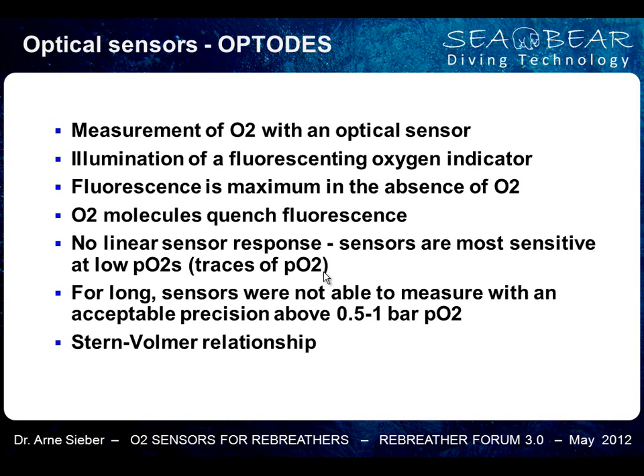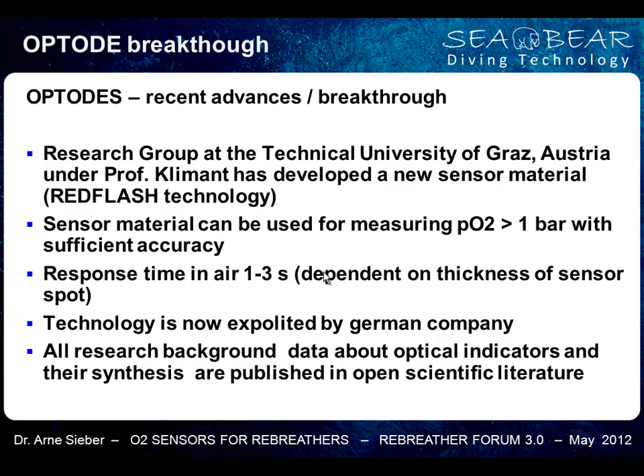Sensors like this have been available for a long time, but they were used for measuring traces of oxygen. For a long time, you could not measure with acceptable precision above 0.5 or maybe 1 bar PO2. But now there came a breakthrough at the Technical University in Graz, where Professor Klimant has developed a sensing material which is less sensitive, and suddenly you can measure PO2s above 1 bar with sufficient accuracy. Response time in air might be 1 to 3 seconds, so quite fast.